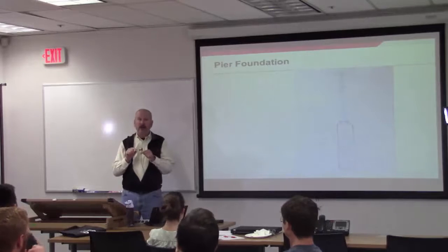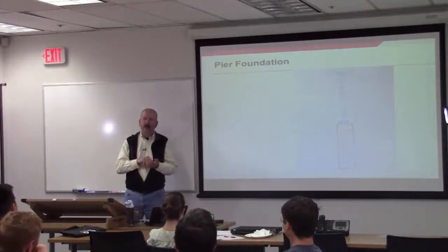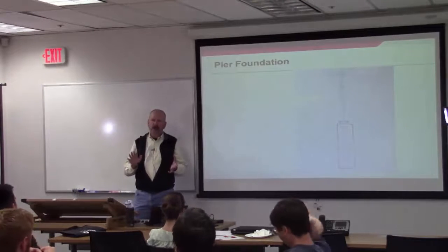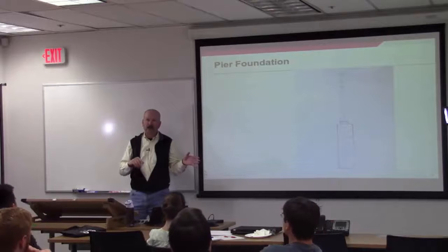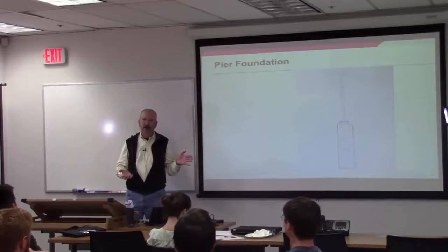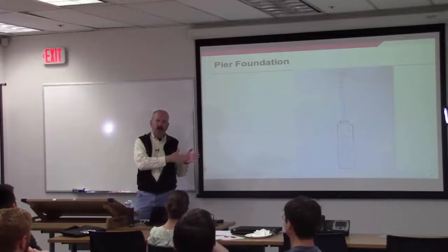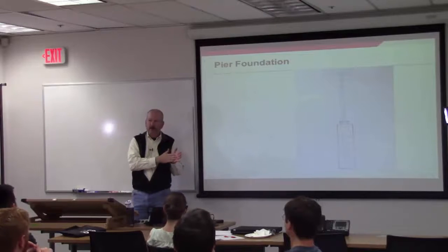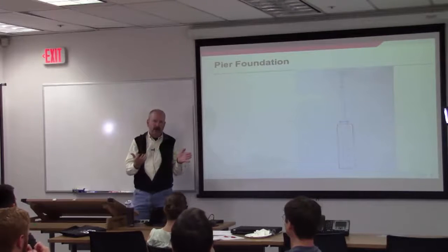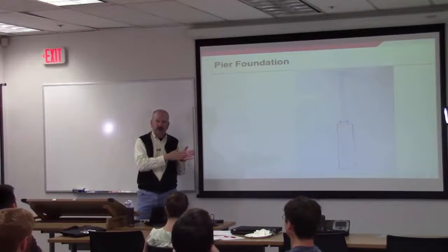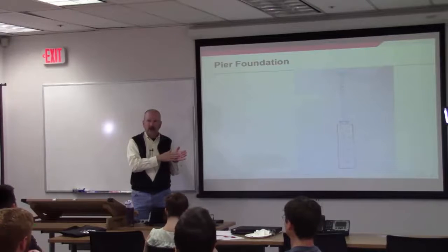If you do not agree with that, right then and there is where you need to raise it with the engineer that made those recommendations. Coming back after the project is done and telling him that you didn't follow his recommendations can often backfire on you, because in some states like California, part of the commissioning process is getting that engineer to sign a letter stating that you followed their recommendations. And it's a really unfortunate argument to have after the fact. Before you've gone down that road is the time to address that.